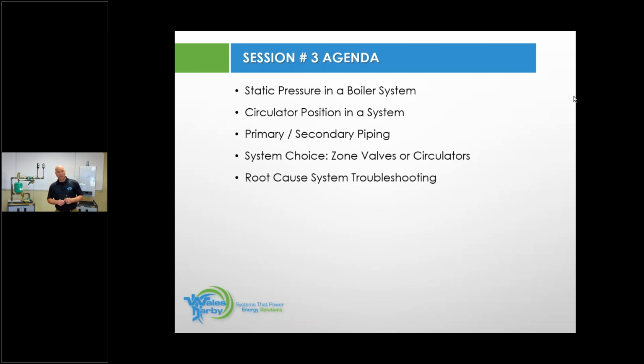Week 3, we were going to cover static pressure in a boiler system. We will put the myth to bed about static pressure in the height of a building, and whether that affects the size of a circulator. We're going to talk about where to locate the circulator. What position do I want it? Do I want it on the supply? Do I want it on the return? Because that's where they've come on boilers for years. Right now, you get them in a box.